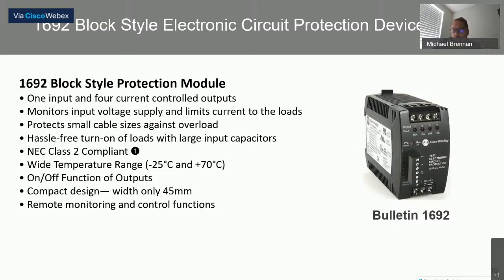And what that allows you to do is run one higher current 24 volt input into the block and have multiple outputs. When you look at the example on the slide, you'll see that it has an input and then 4 10 amp circuits as outputs off of that individual block. So obviously this isn't a Class 2 specific circuit protector, and we'll show you an example. There is a block style that limits you to under 100 VA for each of the 4 outputs. We'll talk about that in a second.